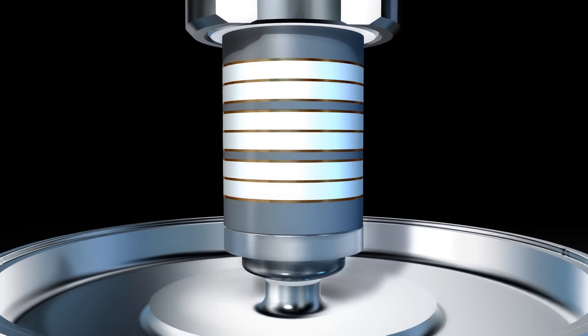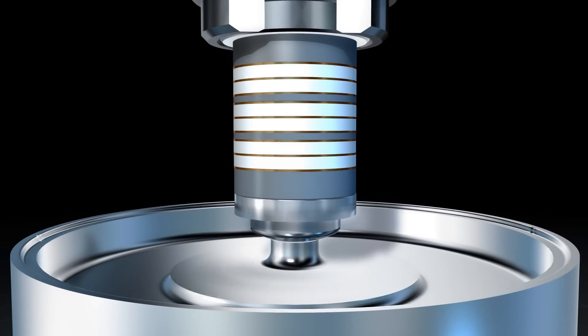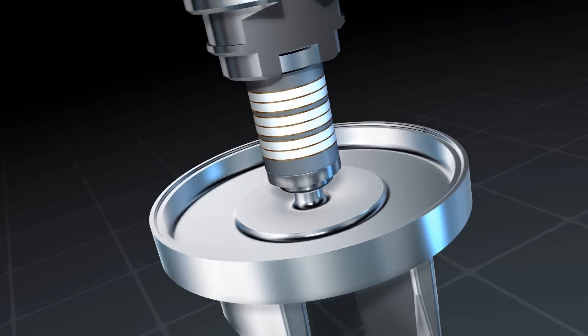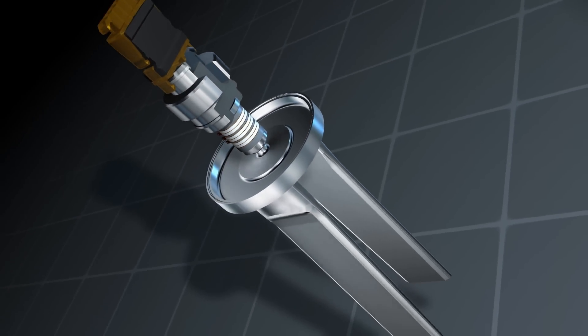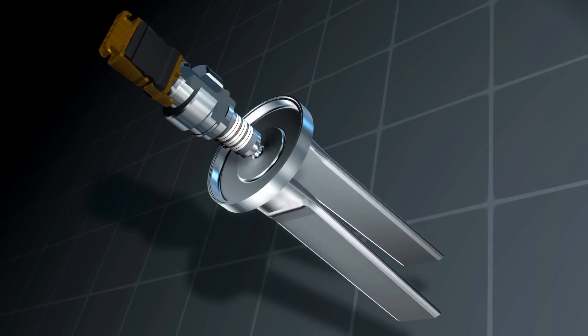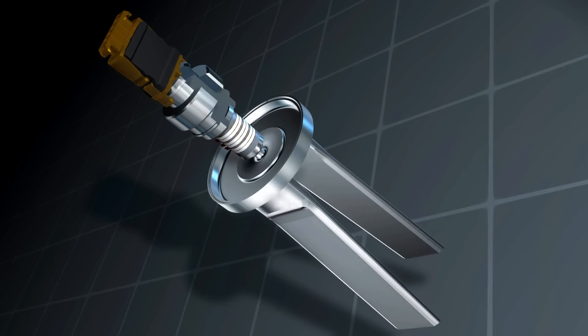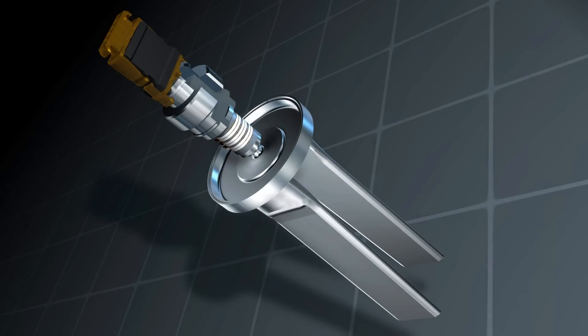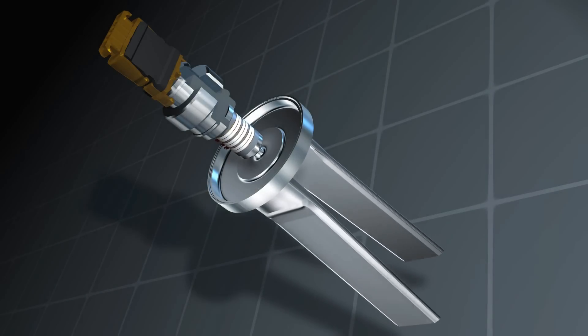As the piezos expand, the membrane is bent to the outside. The ends of the tuning fork, which is attached to the membrane, are pushed apart. As the piezo contracts again, the membrane is bent to the inside. The ends of the tuning forks are pulled together.